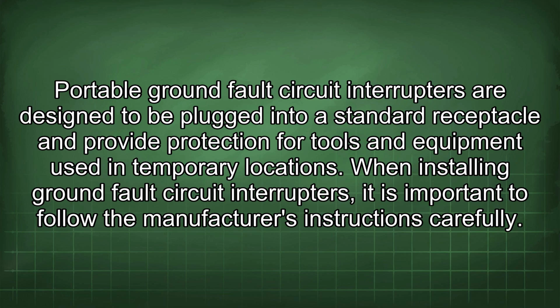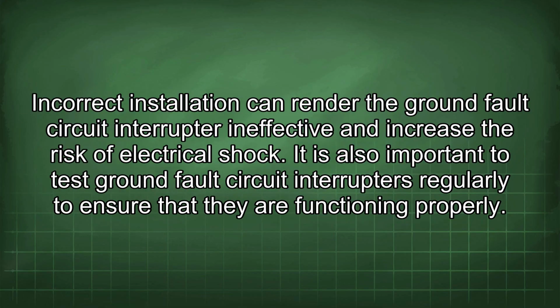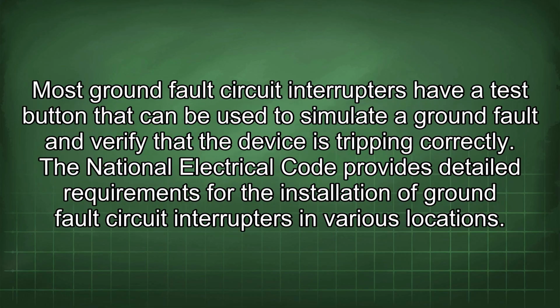When installing ground fault circuit interrupters, it is important to follow the manufacturer's instructions carefully. Incorrect installation can render the ground fault circuit interrupter ineffective and increase the risk of electrical shock. It is also important to test ground fault circuit interrupters regularly to ensure that they are functioning properly. Most ground fault circuit interrupters have a test button that can be used to simulate a ground fault and verify that the device is tripping correctly.